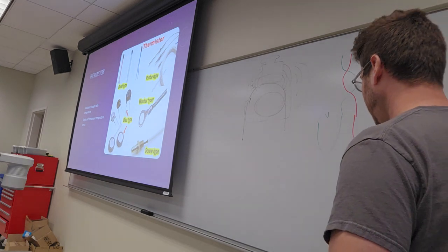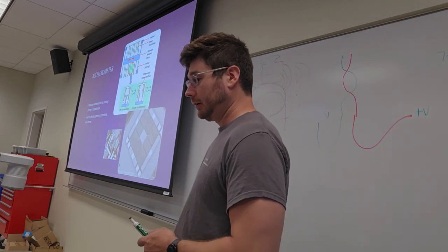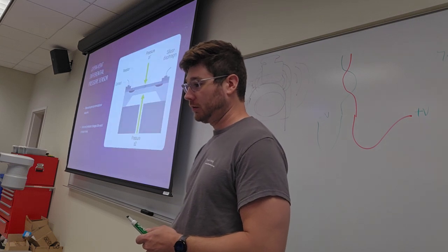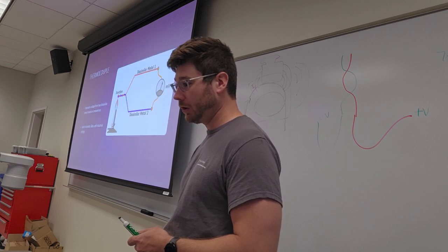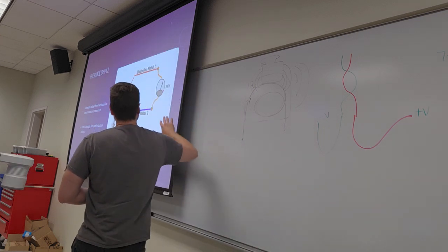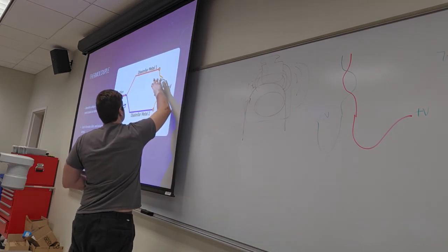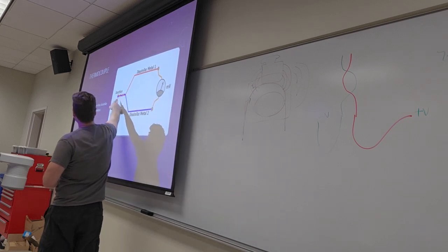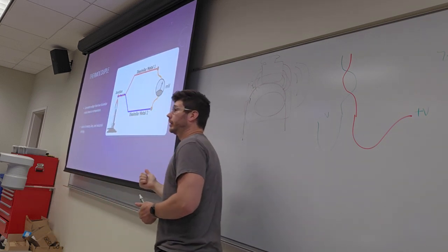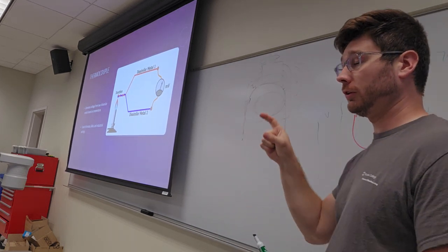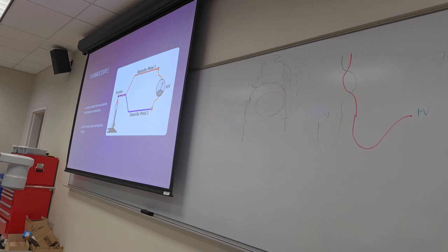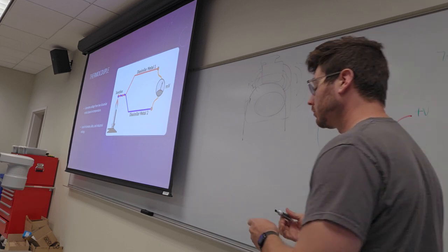So we need an amplifier. We need a device that sits in between our PLC and our raw metal junction that boosts the signal, that amplifies our signal without blowing up the noise. That's a little device that would sit right next to our box, just on our rail, that you would plug the probe into, and that will go into our PLC in order to monitor it.